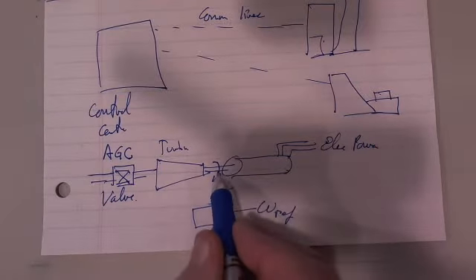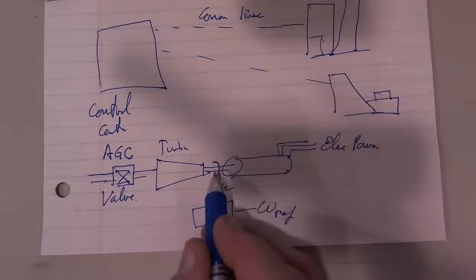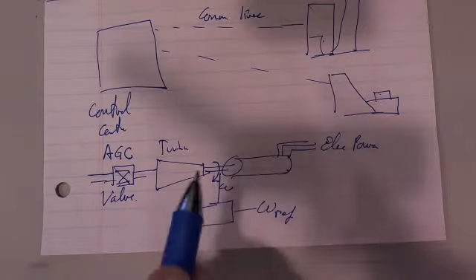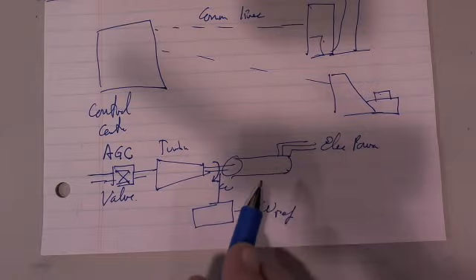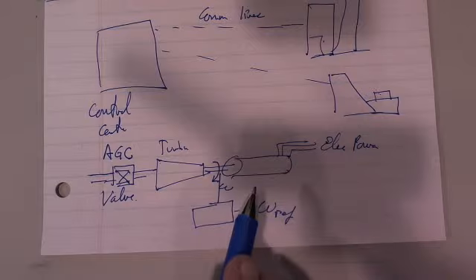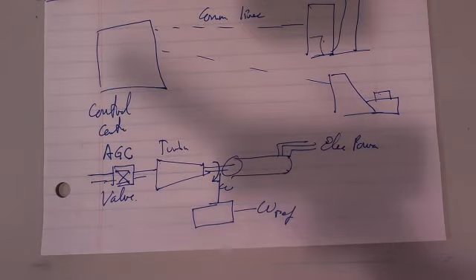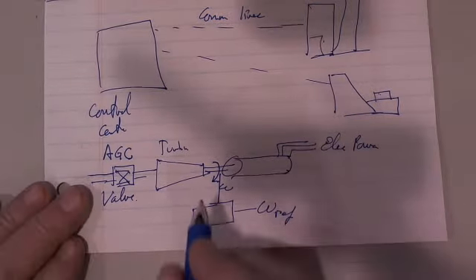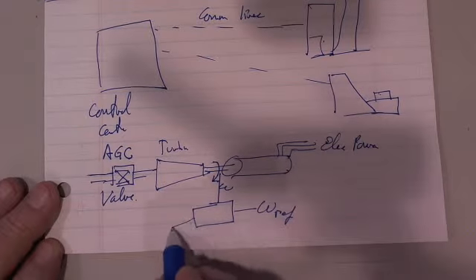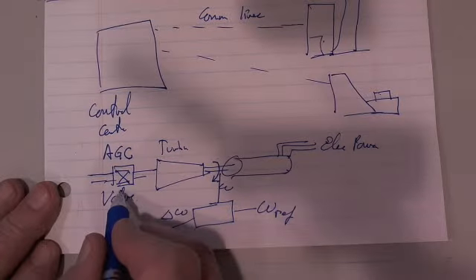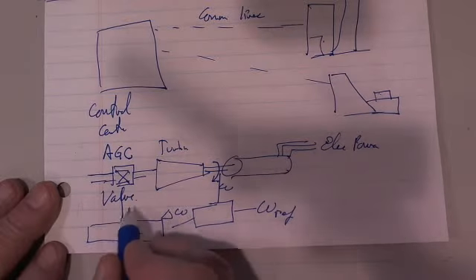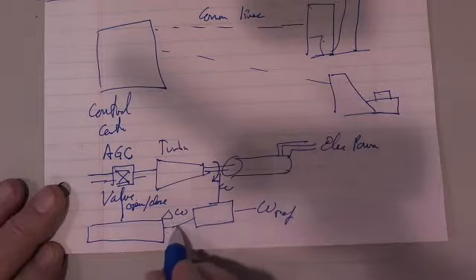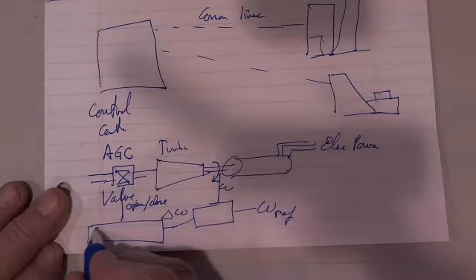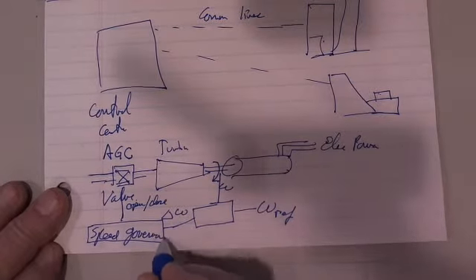How do you measure the speed on the shaft? With digital means, you place very, very accurately ground small notches on the shaft, and you put a light on it, and then a photocell picking it up, and the photocell gets what's equivalent to a square wave, or it gets a blip, blip, blip every time a mark goes by, and you accurately measure digital measurement of the time between the pulses, and average that can be translated depending on the diameter of the shaft, how far, how fast it's rotating. So you now have delta omega, and what you want to do is you want to have a control signal, and the control signal will open, close. And so this is called just a speed governor.